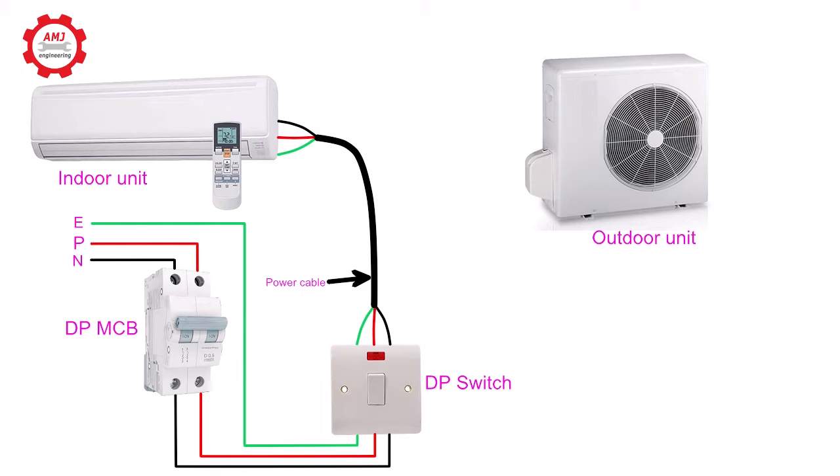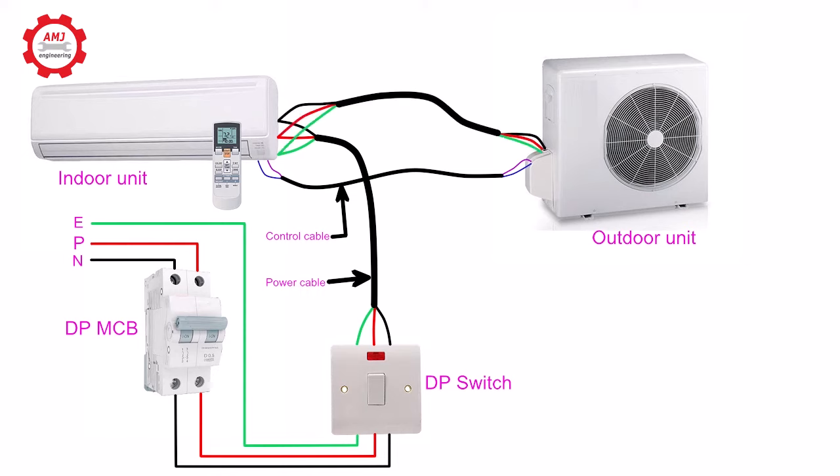There are two cables connected between the outdoor unit and indoor unit of the split AC. The control cable contains two wires and the power cable contains three wires. The power lines first go to the indoor unit, and the power supply is given to the outdoor unit from the indoor unit.